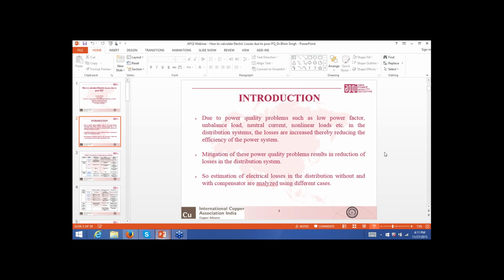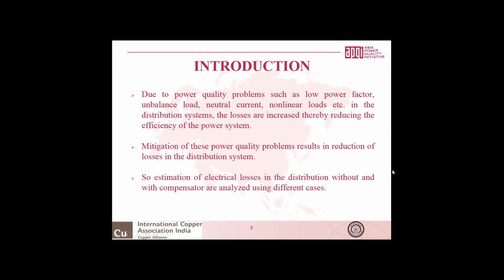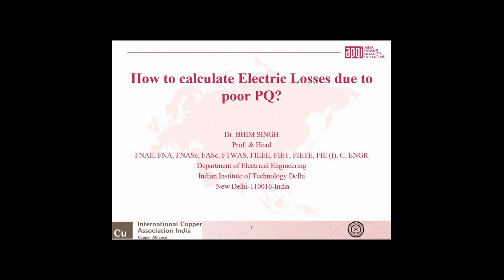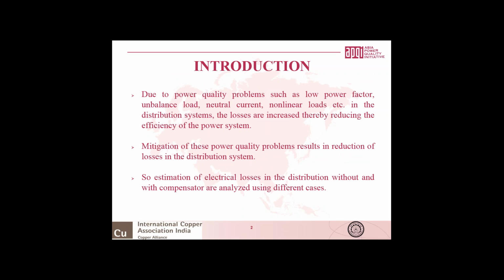Good afternoon, good morning to all of you. I'm Bhim Singh. I'm going to talk about how to calculate electrical losses due to poor power quality. To start with, as an introduction, due to power quality problems such as low power factor, unbalanced loads, neutral current, and nonlinear loads in the distribution system, the losses are increased, thereby reducing the efficiency of the power system. The mitigation of these power quality problems results in reduction of losses in the distribution system. So the estimation of electrical losses in the distribution system without and with compensator is analyzed using different cases.